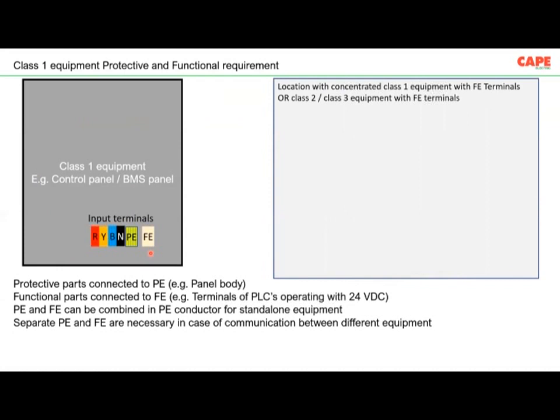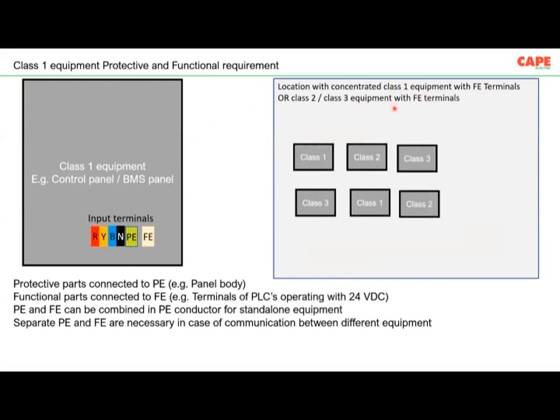A location where concentrated class 1 equipment with FE terminals, class 2 and class 3 equipment with FE terminals, meaning functional earthing terminals. How to make earthing? You have some class 1 equipment, class 2, class 3 equipment. The first one is safety. All the class 1 equipment which has a PE terminal must be connected to the MET, meaning the main earthing terminal or equipotential bonding conductor. So this dotted line, green and yellow, is called protective earthing, which is necessary for class 1 equipment.